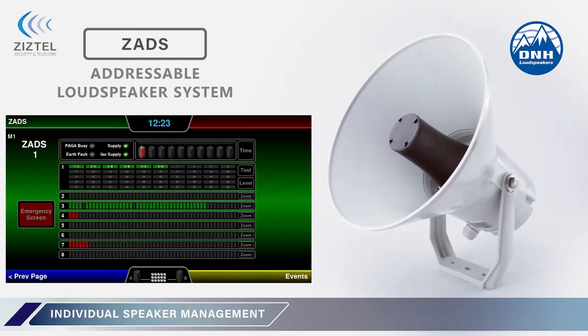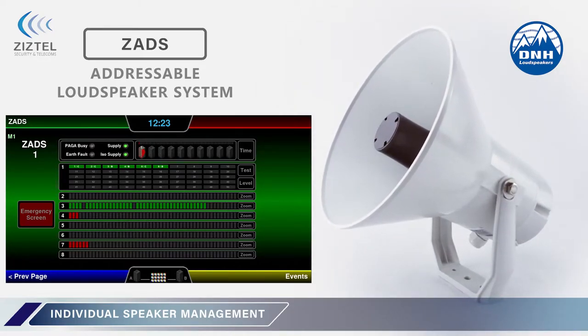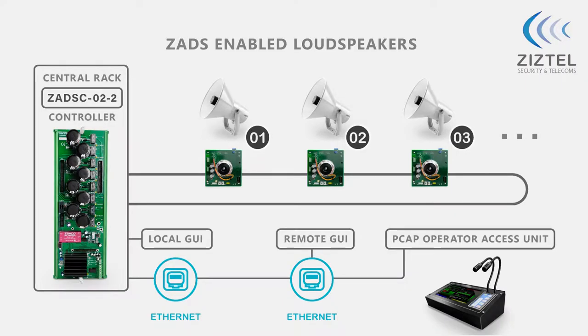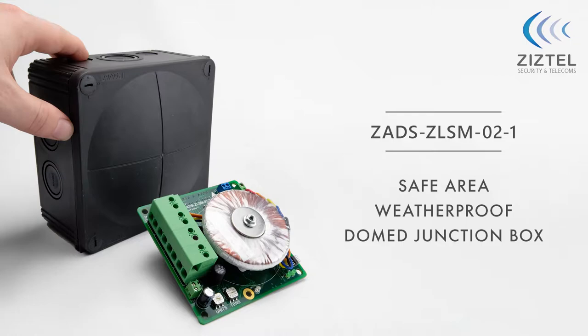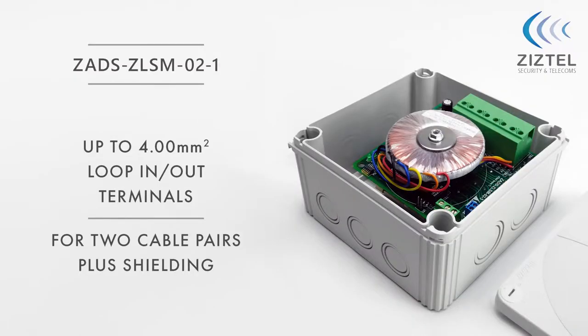The ZADS system enables remote individual loudspeaker supervision and associated volume level setting from a central management position. The ZADS system comprises of two basic components: the ZADSC-02-2 headend, located in the host central PAGA rack, and the ZADS ZLSM2 outstations, located at each target loudspeaker position.